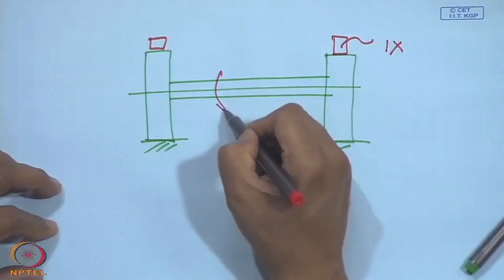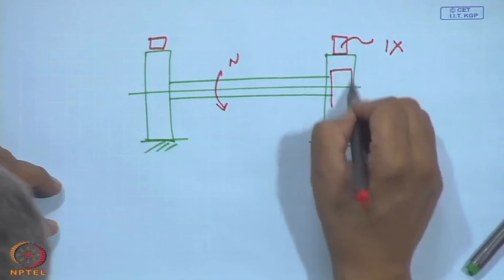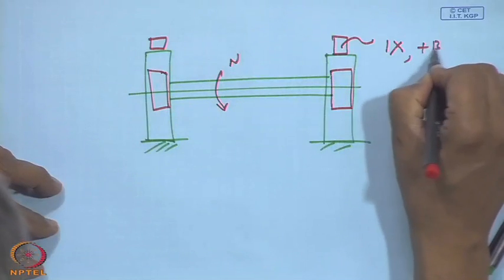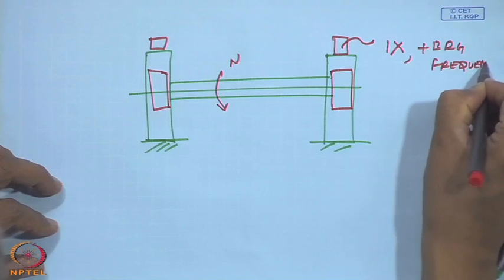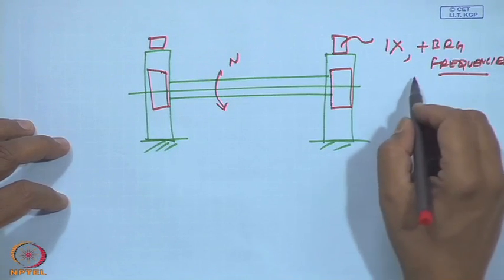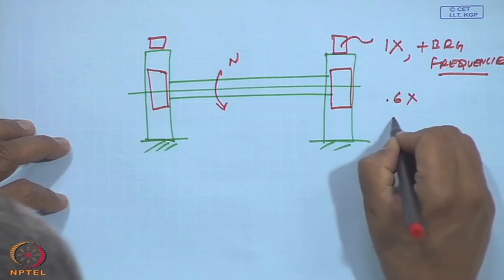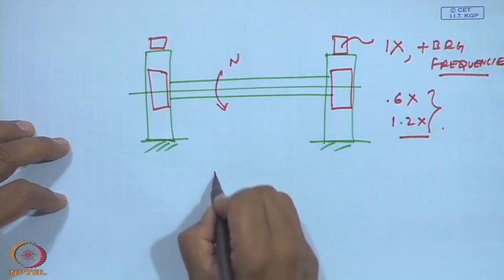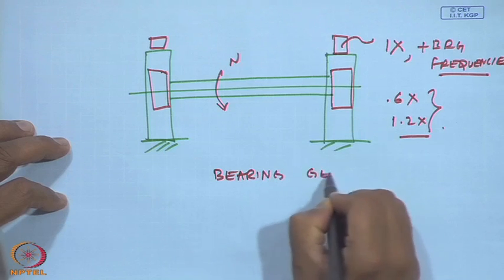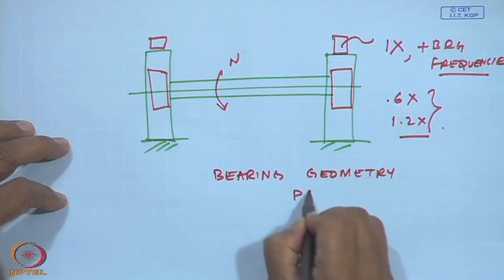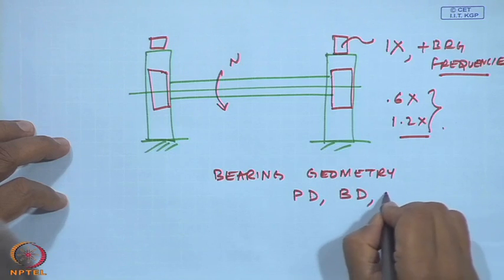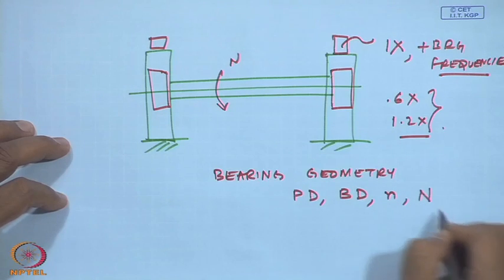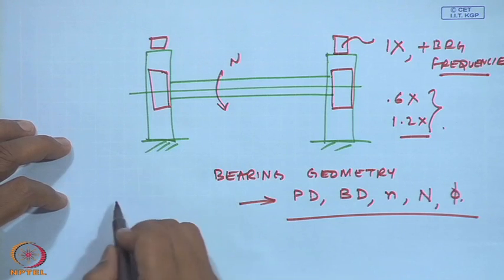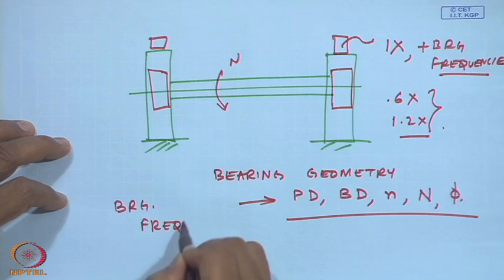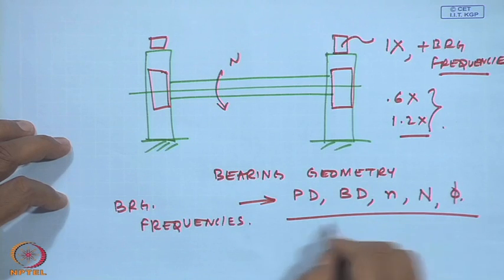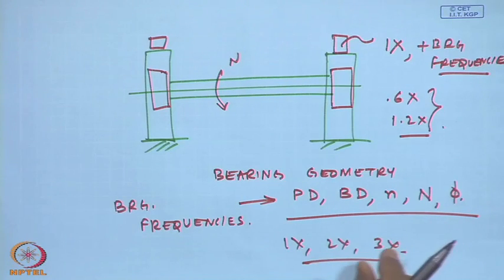The transducer will record the 1x vibration because of the rotational speed, but it will also pick up the bearing frequencies. But you will see that the bearing frequencies you calculate are actually some fractions, either 0.6 of x, 1.2 of x, and they depend on the bearing geometry. By bearing geometry, I mean the pitch diameter, the ball diameter or rolling element diameter, the number of balls, small n, the rotational speed, and the contact angle. So, these frequencies are in no way related to 1x, 2x, 3x, which we saw in the case of rotating shafts.